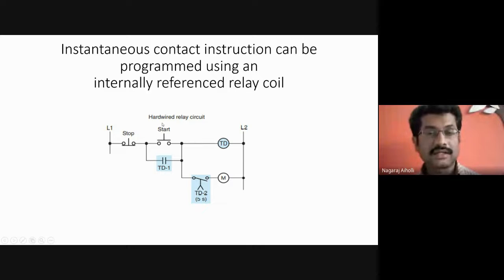If the switch is released, the current cannot flow, there is no continuity, and the circuit becomes discontinuous. Hence, after the start is released, TD1 is used as the seal-in contact to maintain the current in the circuit. You have studied seal-in contacts, is it not? Their function is to maintain the conduction current even after the start switch is released.